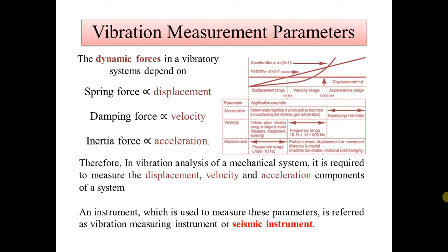The instrument basically used for vibration measurement is called a seismic instrument. Now when we compare these three instruments, the displacement instrument is a low frequency instrument, with a range up to 10 hertz. The velocity instrument measures vibration in the range of 10 hertz to 1000 hertz. And for high frequency, generally we use the acceleration instrument, that is the accelerometer.